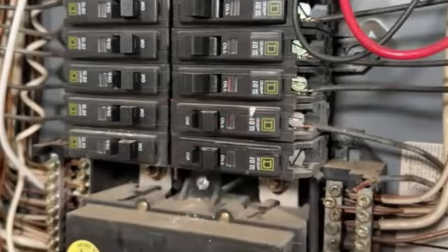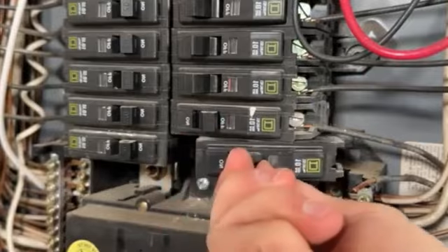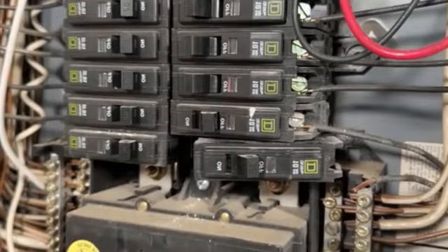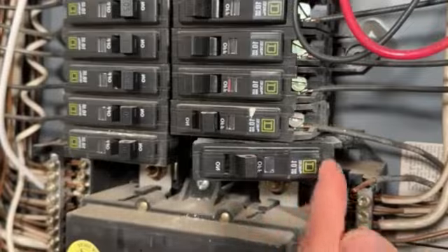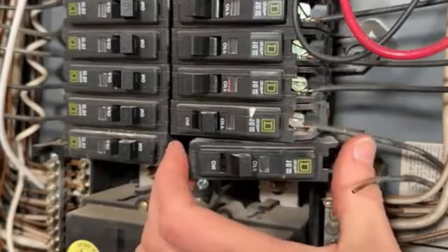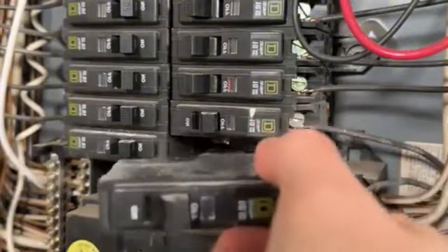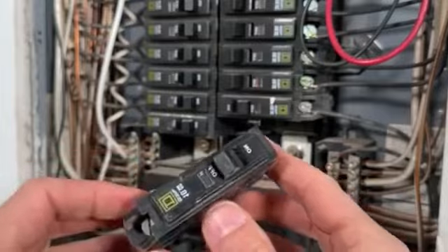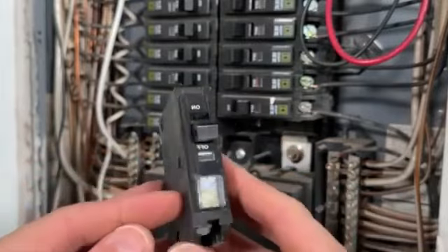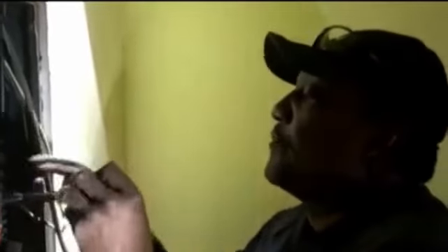2. Test every AFCI breaker in your panel monthly. Press the test button. The breaker must trip immediately. If it does not trip, the internal electronics have failed and the breaker will not protect you. Replace it with a commercial-grade AFCI from Eaton, Siemens, or Square D, not the builder-grade $28 version. Cost $50 to $70 per breaker. 3. Check your panel label. If you see Federal Pacific Electric, Zinsco, or Sylvania/Zinsco, schedule replacement immediately. Do not wait for a failure. The failure will be a fire. Cost $1,800 to $3,500 for full panel replacement with modern breakers.